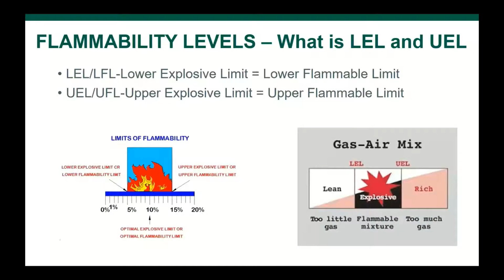So flammability levels. We've been talking about LEL and LFL, which are synonymous: lower explosive limit, lower flammable limit, and you have the upper explosive limit and the upper flammable limit. What's the OSHA definition? OSHA says that the LEL, lower flammable limit or lower explosive limit, means the minimum concentration of a substance, gas, vapor, or mist in the air needed for an ignition source to cause a flame or explosion. What is the UEL? It is the maximum concentration of a substance in air in which an ignition source can cause a flame or explosion.